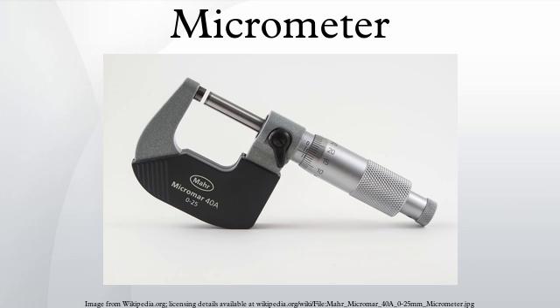Not all calibration is an affair for metrology labs. A micrometer can be calibrated on site anytime, at least in the most basic and important way, by measuring a high-grade gauge block and adjusting to match. Even gauges that are calibrated annually and within their expiration time frame should be checked this way every month or two, if they are used daily. They usually will check out okay as needing no adjustment.